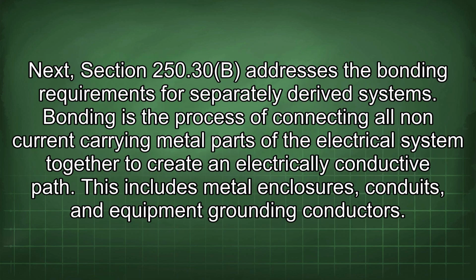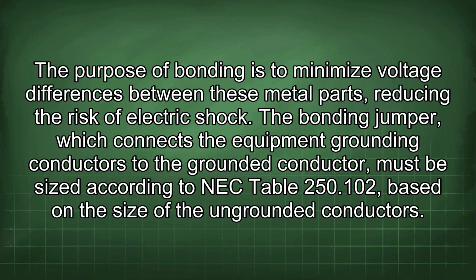Next, Section 250.30(B) addresses the bonding requirements for separately derived systems. Bonding is the process of connecting all non-current carrying metal parts of the electrical system together to create an electrically conductive path. This includes metal enclosures, conduits, and equipment grounding conductors. The purpose of bonding is to minimize voltage differences between these metal parts, reducing the risk of electric shock.